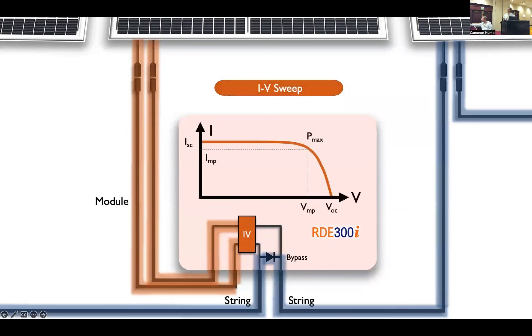But during a brief time slice, every so often, we're going to perform an IV sweep on that module. So that module is temporarily disconnected from the array as shown here in orange and blue — the array is bypassed — and we get an IV sweep. From that IV sweep, we can determine the typical IV parameters: ISC, Pmax, VOC, et cetera, anything you can get from an IV sweep. That whole process takes a little less than half a second. We also have some faster modes, so the inverter never really notices that that module is gone.